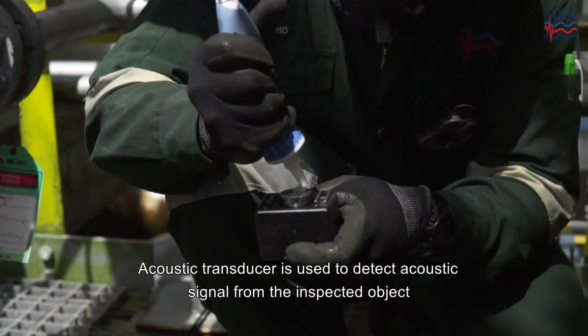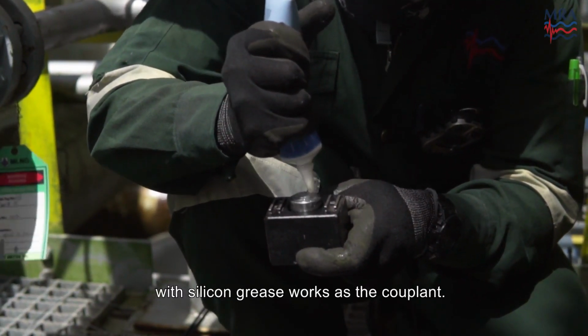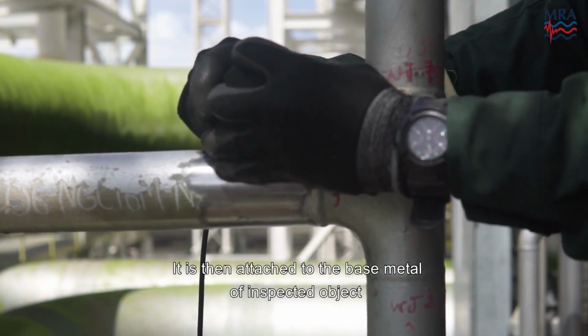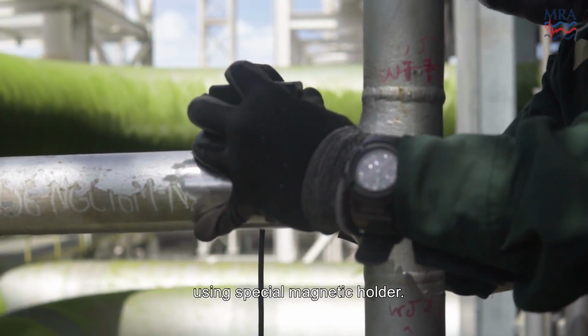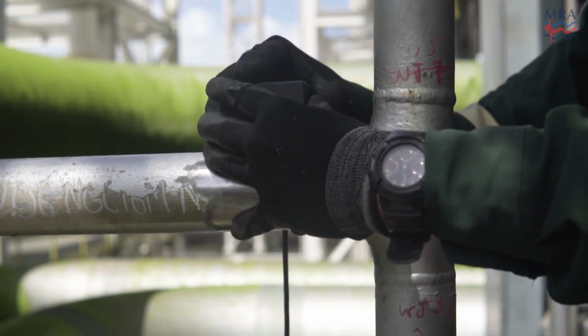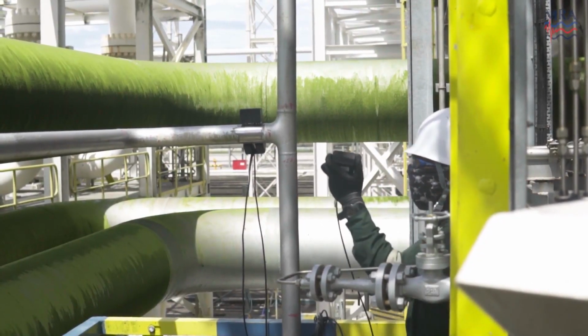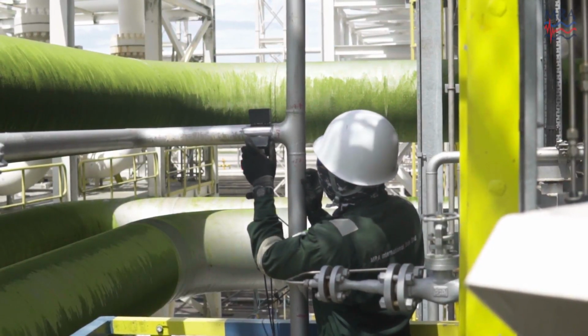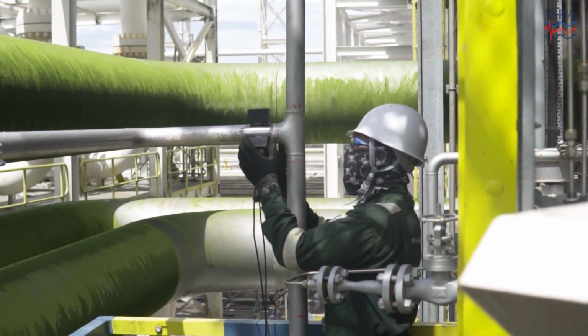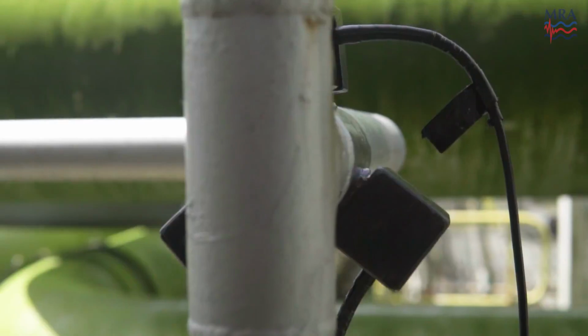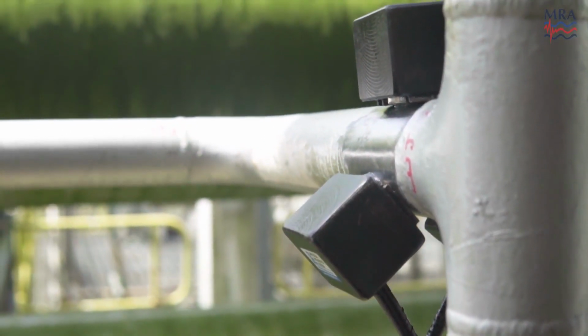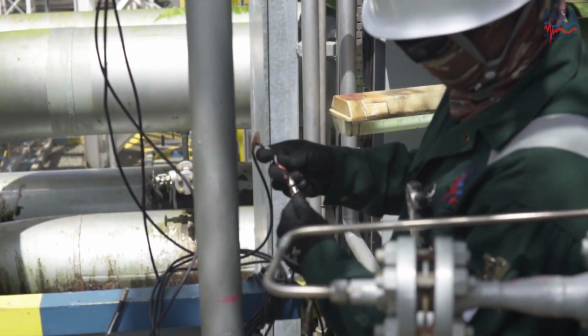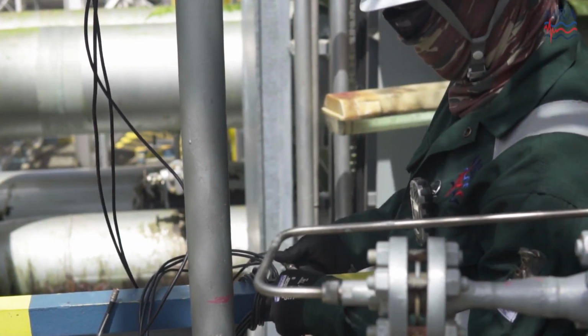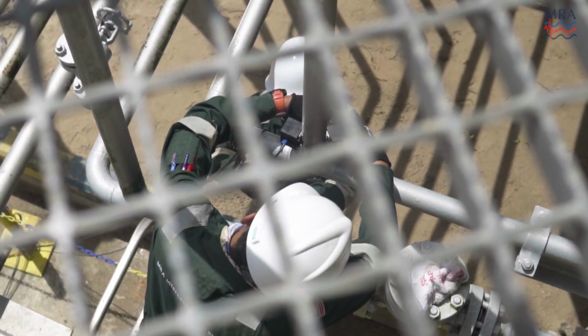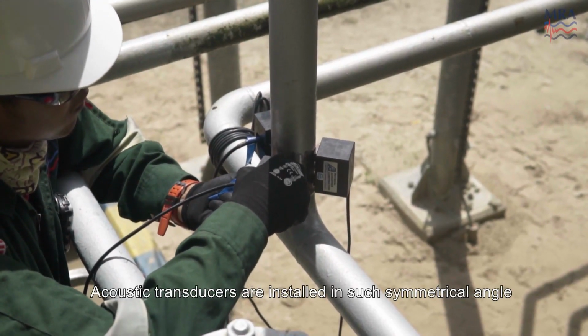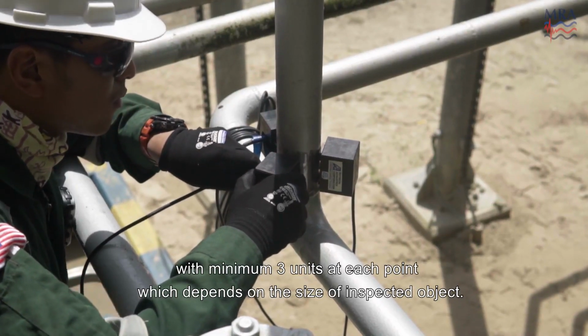Acoustic transducer is used to detect acoustic signal from the inspected object with silicone grease works as a couplant. It is then attached to the base metal of inspected object using special magnetic holder. Acoustic transducers are installed in such symmetrical angle, with minimum 3 units at each point, which depends on the size of inspected object.